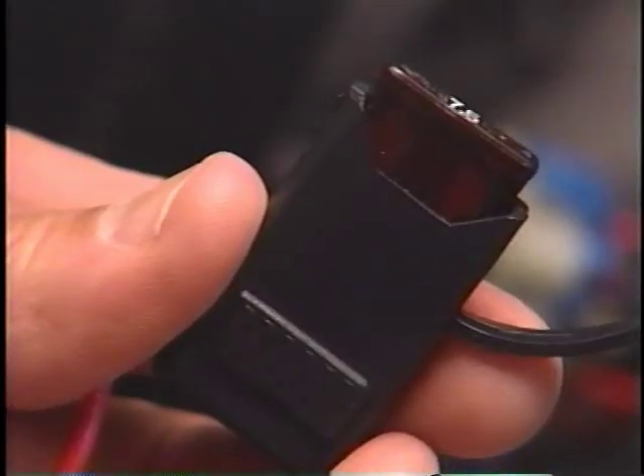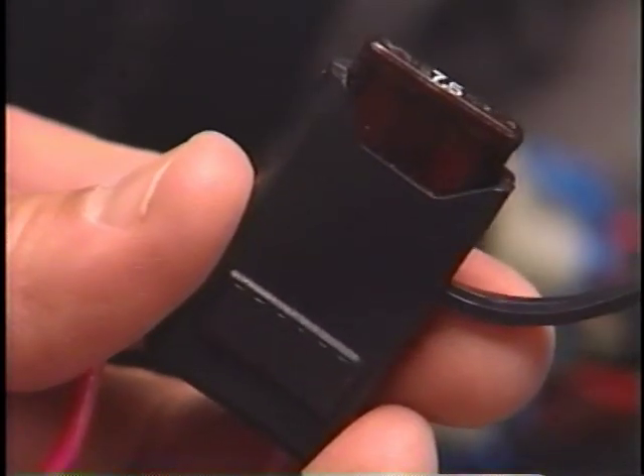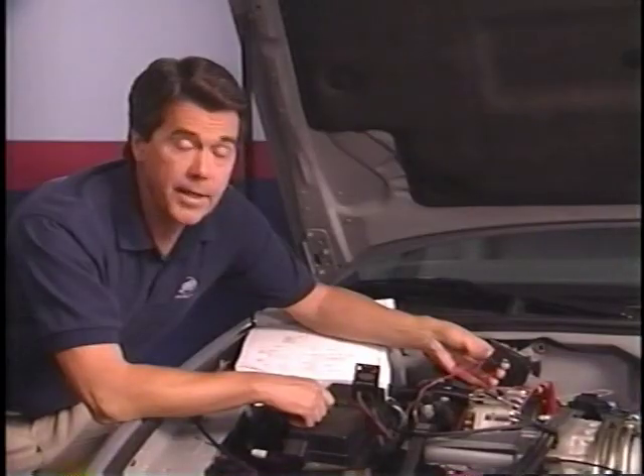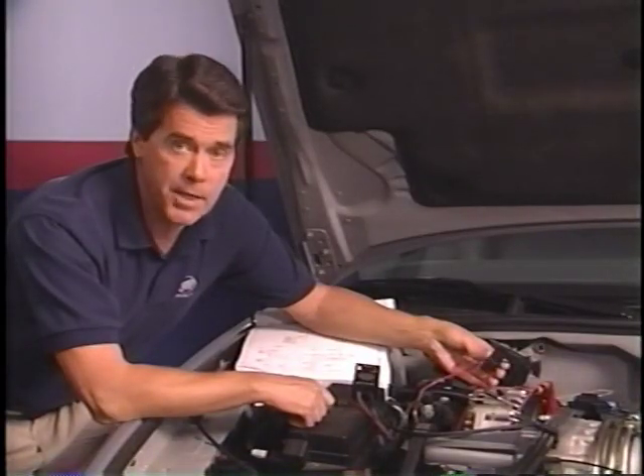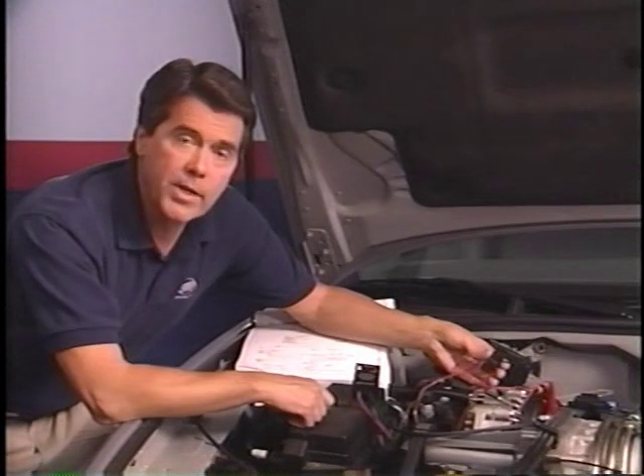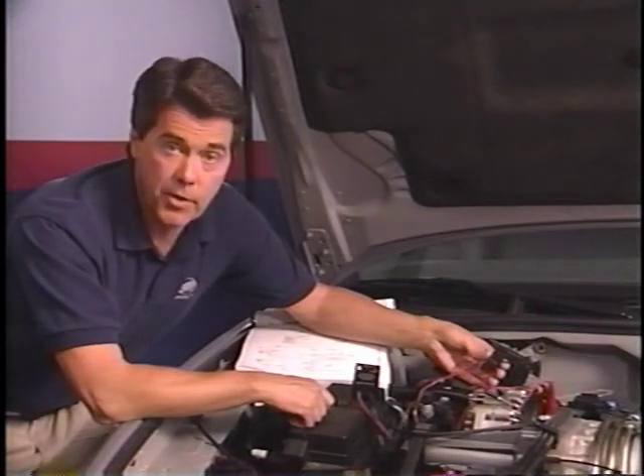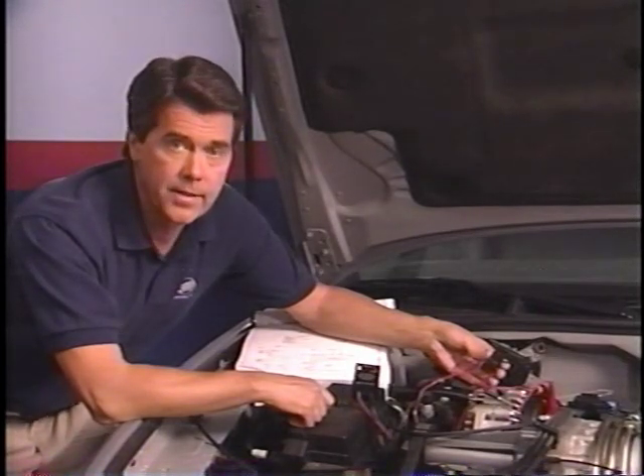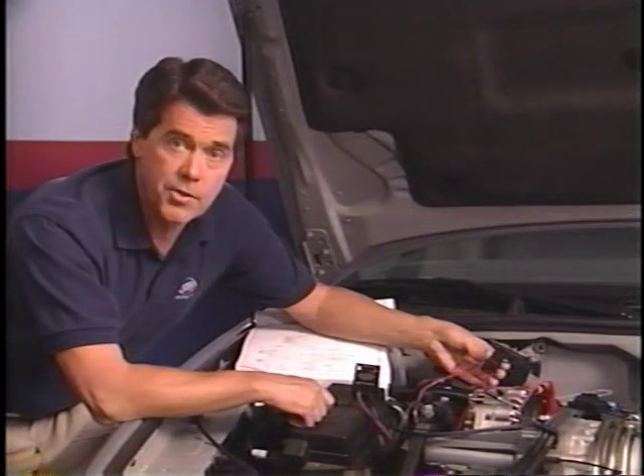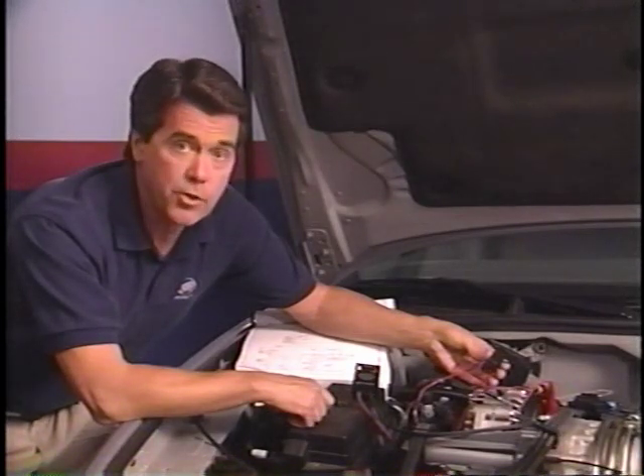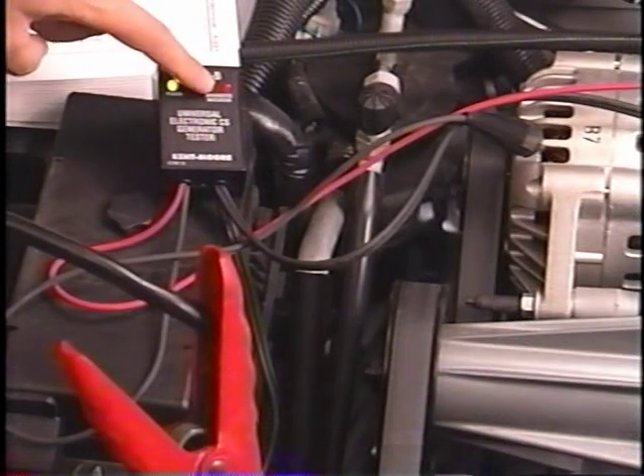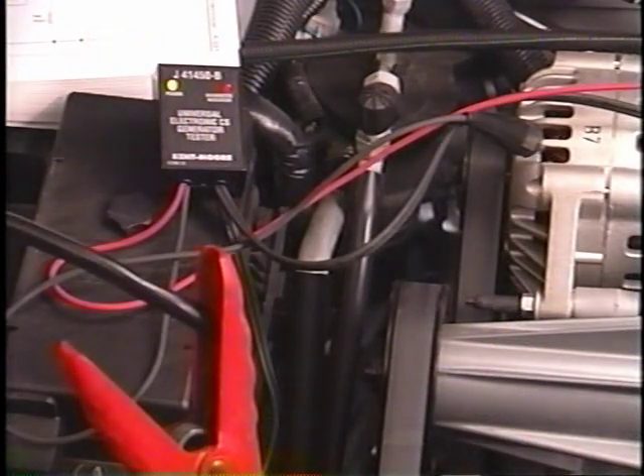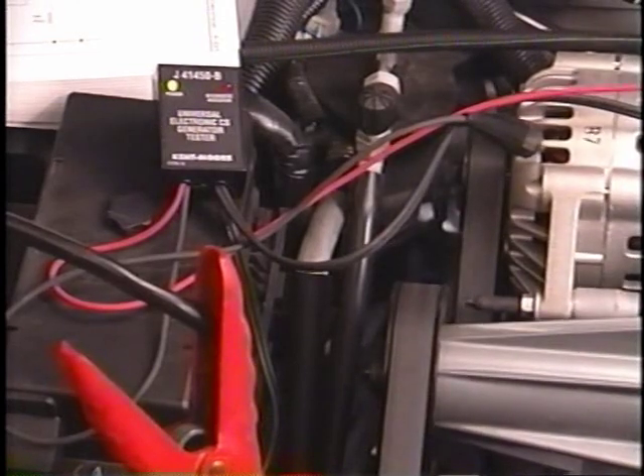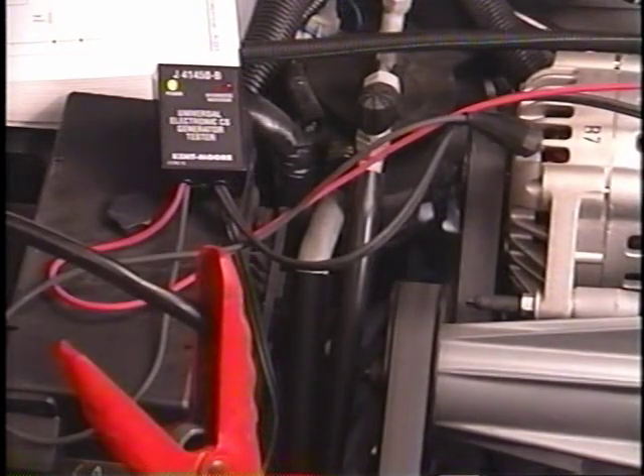However, if the fuse does blow, the L circuit is shorted to power. It's miswired or it has improper resistance. Regardless, excessive power on the L circuit has wrecked the regulator. The wiring concern on the L circuit must be fixed prior to installing a new generator. If the red LED is on, switch off all accessories and start the engine. If the red LED stays on, replace the generator.